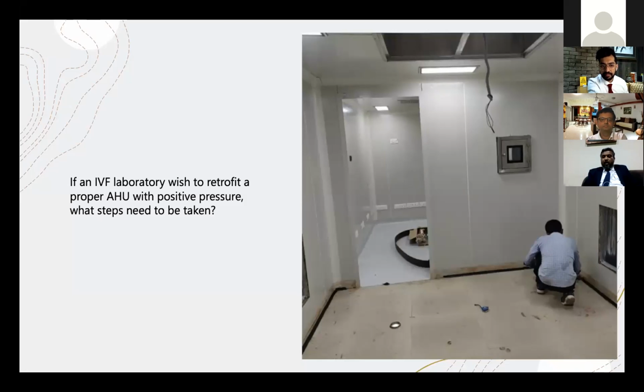And to balance the air, we need four walls — we cannot have a partition in between. So that's a technical challenge, unfortunately. If you want to mix up the air, that's a clinical issue. I don't think mixing different quality air from one room into another room will give you the required air quality in both rooms. So that's what, technically, I wanted to tell you.